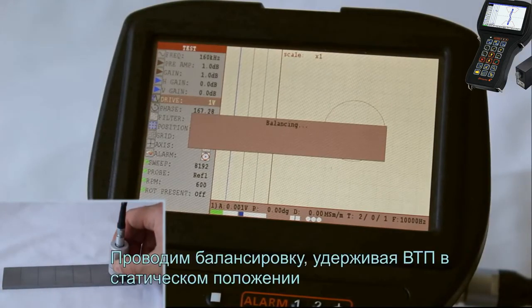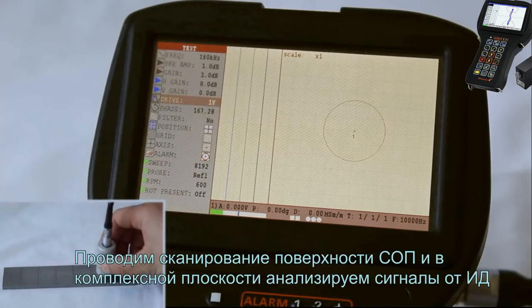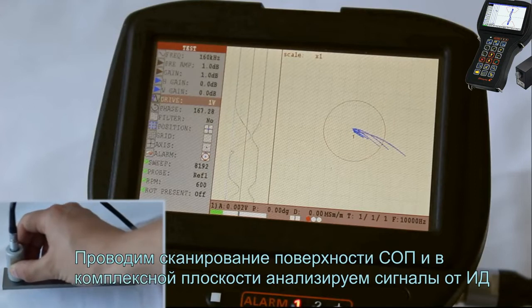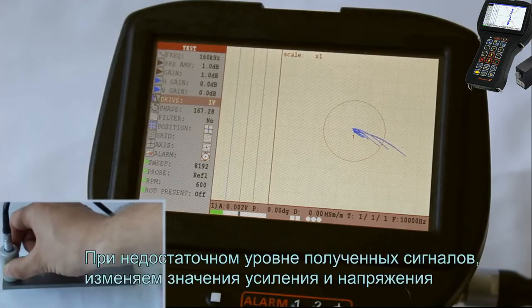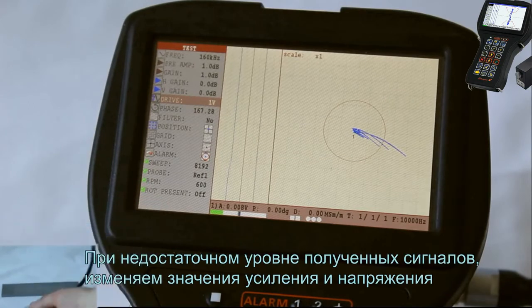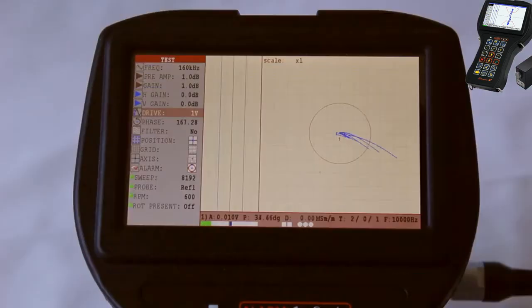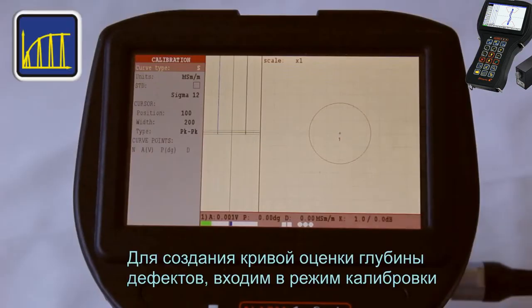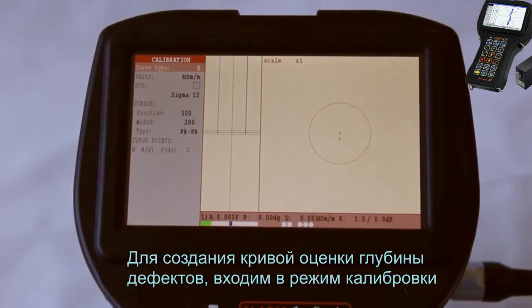Perform the balancing by holding the probe in a static position. Scan the block surface and, in a complex plane, analyze the signals received from the artificial defect. If the level of received signals is low, change the gain and voltage values. To plot the curve for depth estimation, enter the calibration mode.